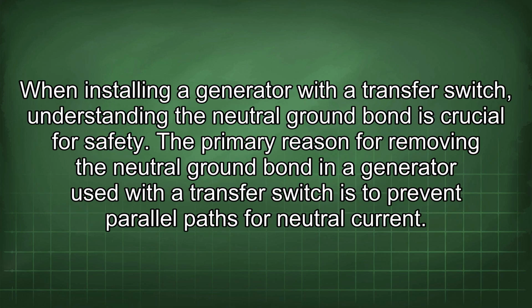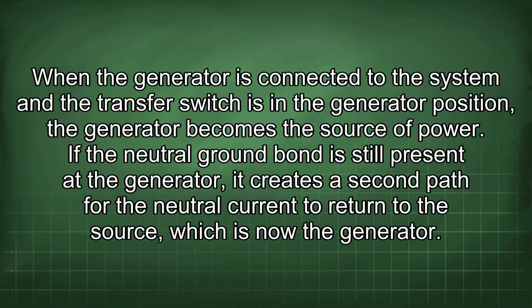When installing a generator with a transfer switch, understanding the neutral ground bond is crucial for safety. The primary reason for removing the neutral ground bond in a generator used with a transfer switch is to prevent parallel paths for neutral current. When the generator is connected to the system and the transfer switch is in the generator position, the generator becomes the source of power. If the neutral ground bond is still present at the generator, it creates a second path for the neutral current to return to the source, which is now the generator.